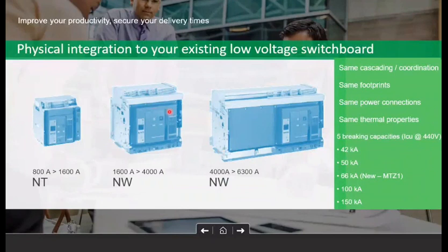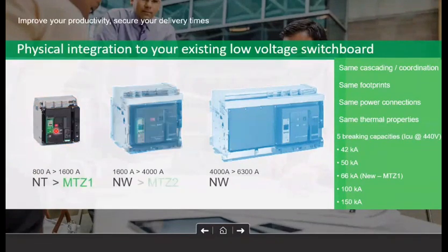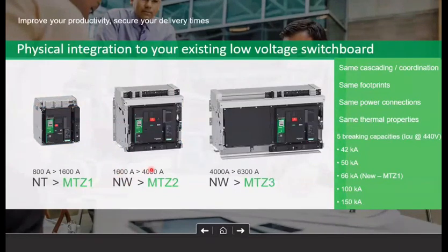As MasterPact MTZ is the third generation of breaker, it has the same footprint, same cascading and coordination chart, same power connection, and same thermal properties as NT and NW. You can see here that earlier we had an NT from 800 ampere to 1600 ampere, which has been replaced by a new range, MTZ1. Then in place of NW frame 1, from 1600 to 4000 ampere, we have MTZ frame 2. Then, in place of NW frame 2, we have MTZ3 from 4000 to 6300 ampere.